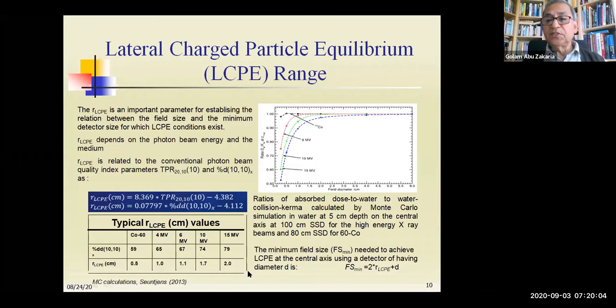What is important in these slides, you can see how you select your detector for given fields. And this is the relation: the minimum field size is equal to 2 times the radius plus the diameter of the detector. So when you know the detector diameter, you can also define the field size which allows you lateral charged particle equilibrium.